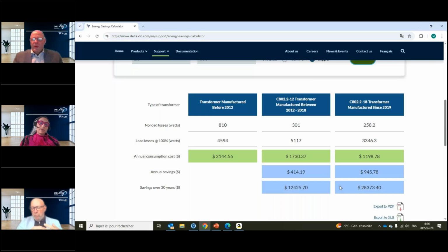So your electrical room will be easier to temperature control, with less heat rejection in the room. So everybody's gaining, and also from the energy saved within the transformer. Over here you have like 5,300 watts of losses, and in this one you have like 3,500 watts of total losses. So this is one transformer.